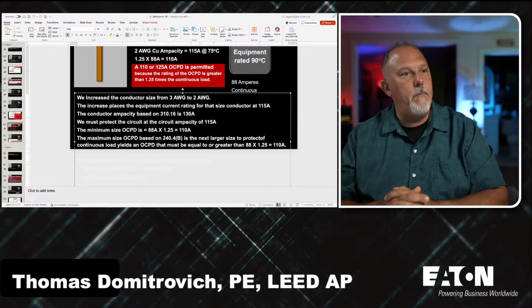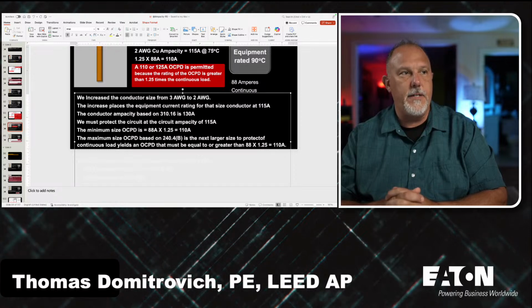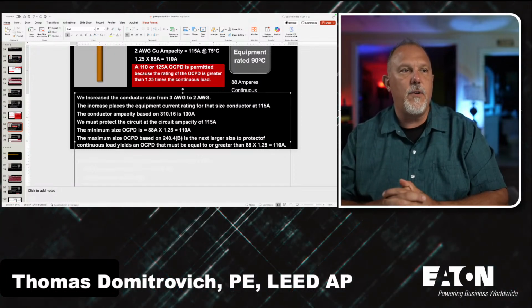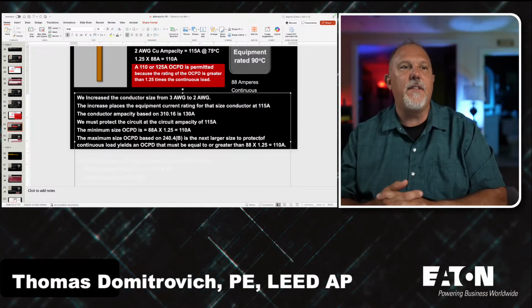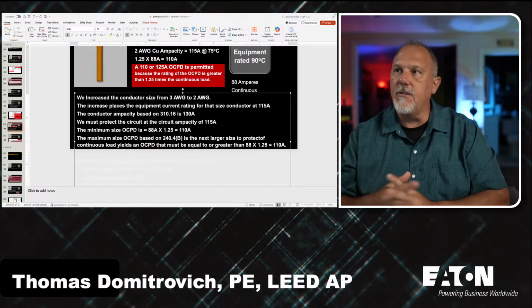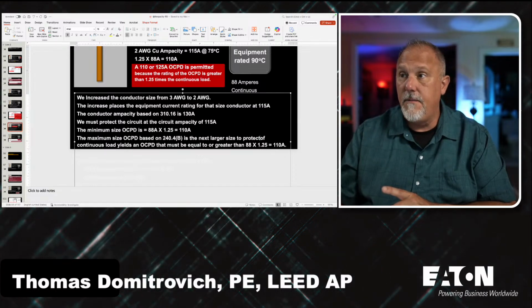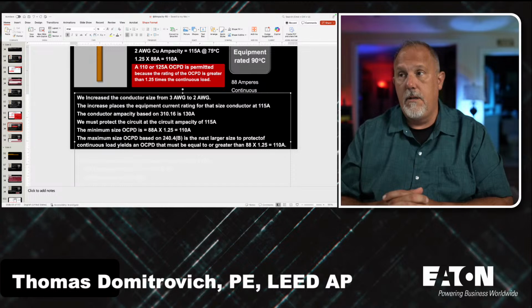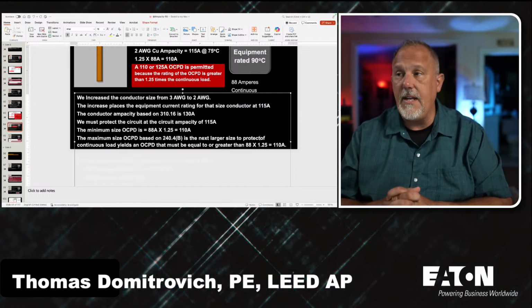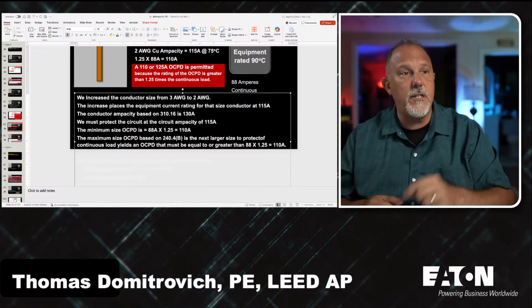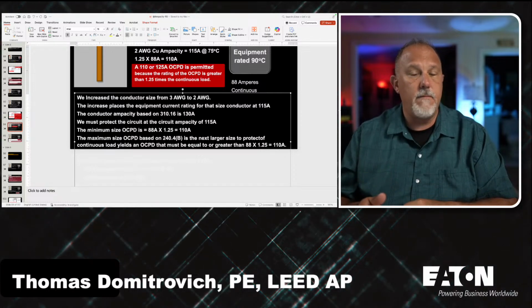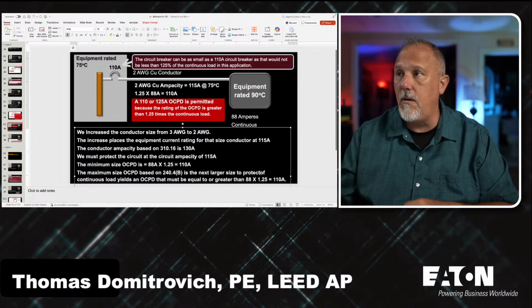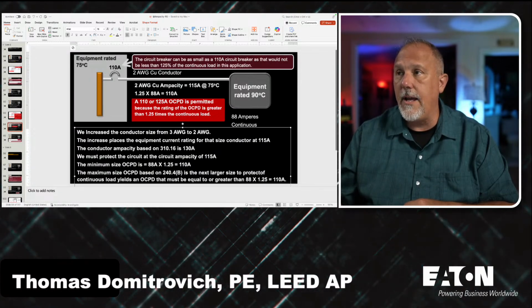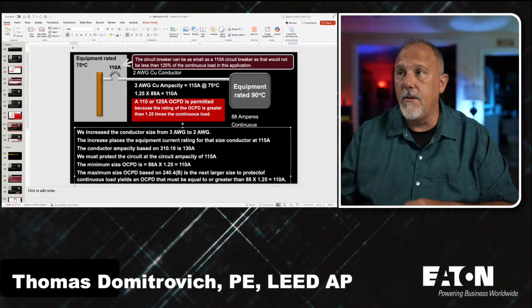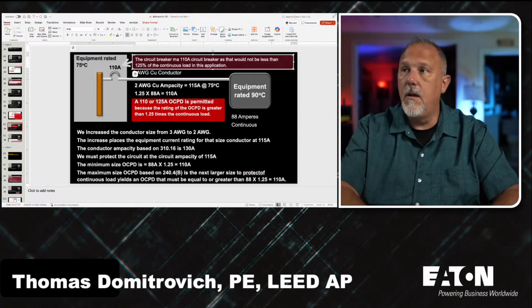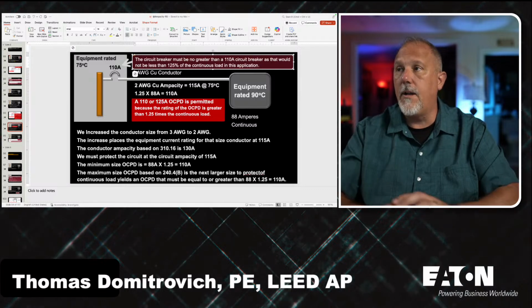Ooh, this opens up a bag of worms here, Dawn. It says the next higher standard overcurrent device rating above the ampacity of the conductors. In this case, the ampacity of the conductor is 130 amps. The ampacity of the circuit is only 115. I don't have any permission to exceed the ampacity of the circuit. So I can't go. This is wrong. The circuit breaker can be as small as a 110 amp circuit breaker. The circuit breaker must be no greater than a 110 amp circuit breaker.